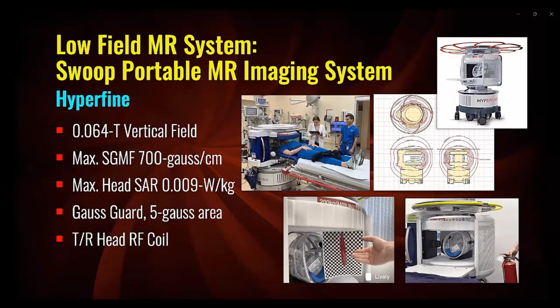Because of its innovative design, there are no major issues related to ferromagnetic objects becoming missiles or projectiles, as shown by this box cutter and fire extinguisher, both of which are made of ferromagnetic materials. Watch what happens when these items are brought up close to the Swoop MR system. For the box cutter, there is barely any attraction to the 0.064 static magnetic field, while the fire extinguisher exhibits virtually no magnetic field related issues.